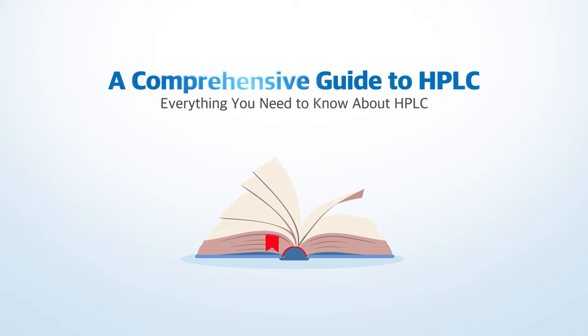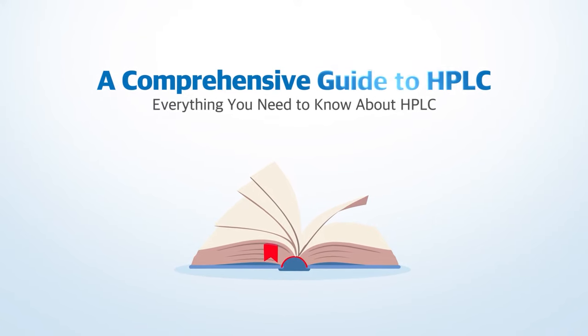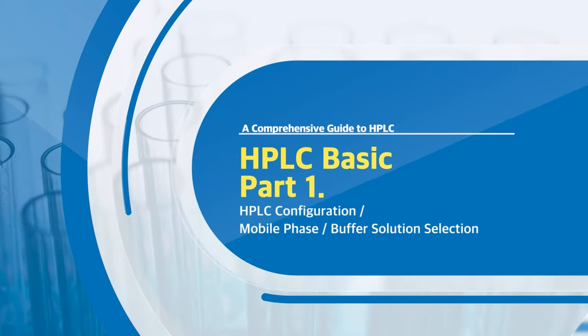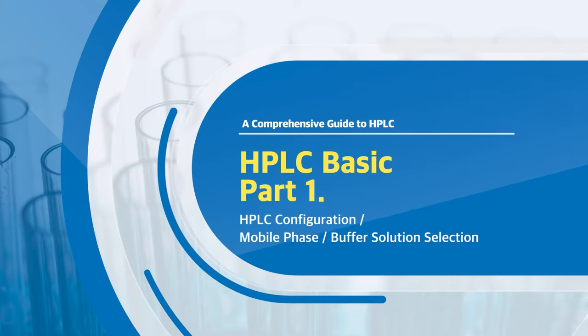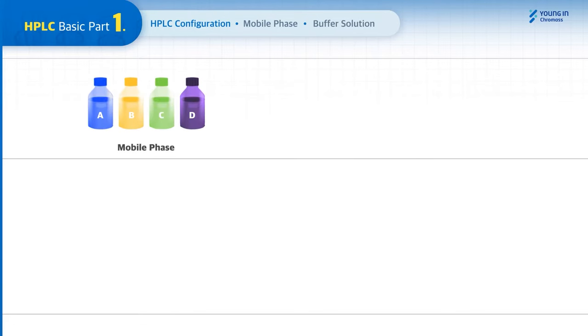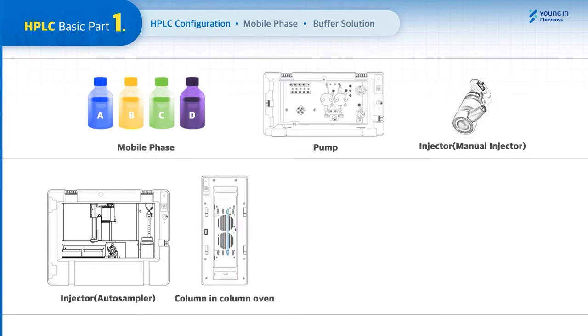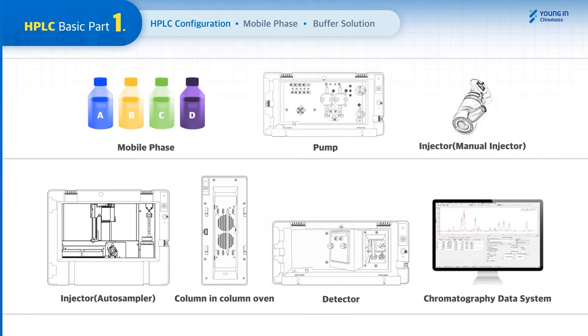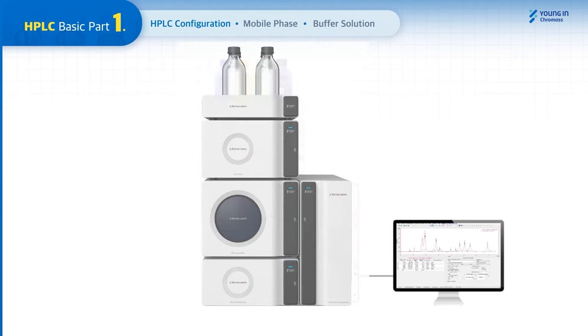A comprehensive guide to HPLC. Generally, HPLC is configured with a mobile phase, a pump (also called a solvent delivery module), an injector which can be either a manual injector or auto sampler, a column, a detector, and a CDS chromatography data system. Once each module is configured into an HPLC system, it can show how the flow goes through the HPLC.